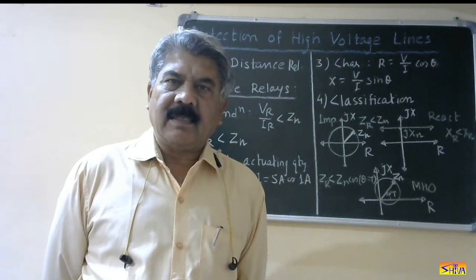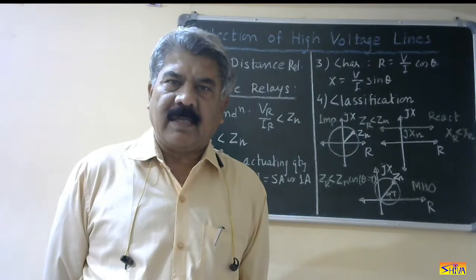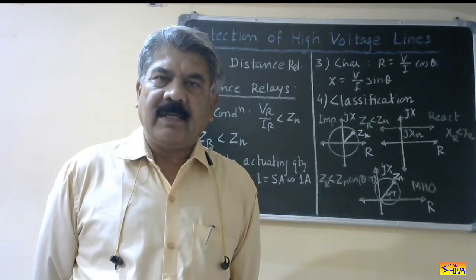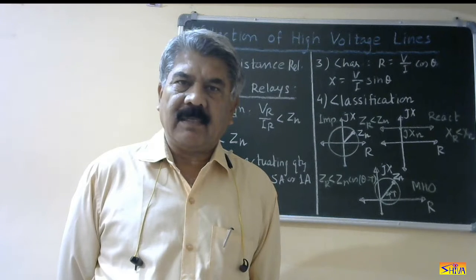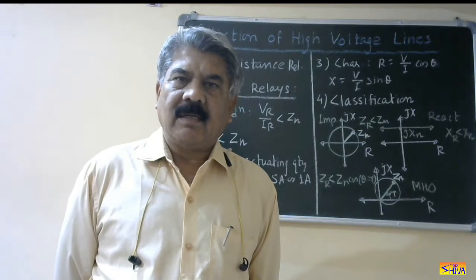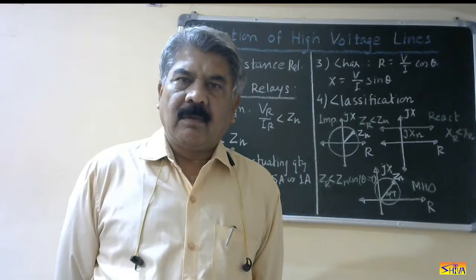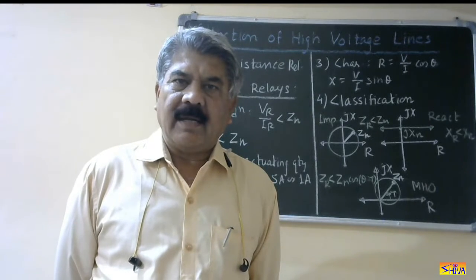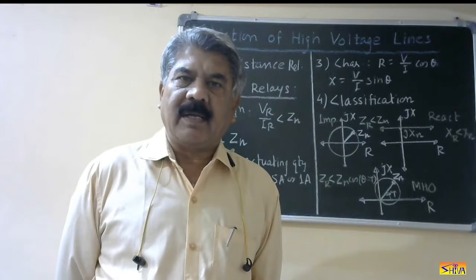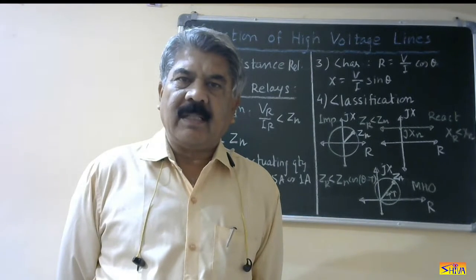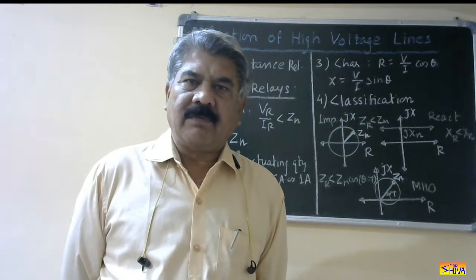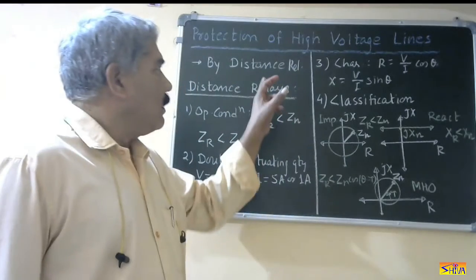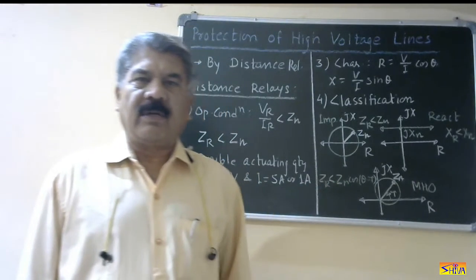In my last class, I had explained the requirements of protection system for high voltage lines. We have seen that for high voltage lines, we require a protection system which acts very fast, which provides effective backup protection, good selectivity, and can make arrangement to operate the circuit breaker at both ends simultaneously to retain the transient stability of the system. So if we look at all these requirements, we find that distance relay is the best relay for protection of high voltage lines.